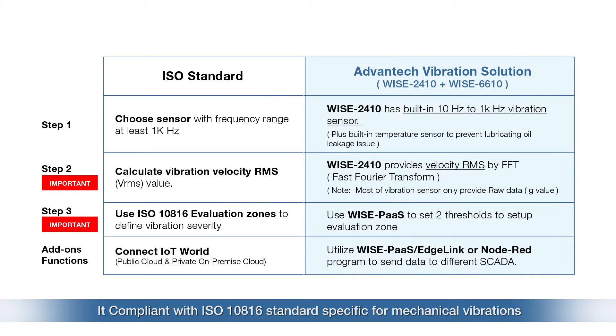The WISE-2410 complies with ISO 10816 standard specified for mechanical vibration, covering measurement of vibration velocity and severity for machines such as pumps, fans, compressors, and so on. It operates in the 10 to 1000 Hz frequency range. It also supports an IP66 design, using an IP66 waterproof case to increase its robustness in hazardous and dusty indoor/outdoor environments.